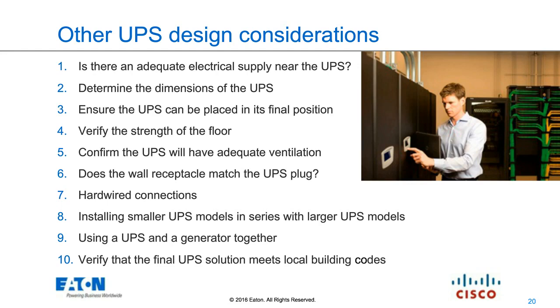And we see this a lot. This question comes up often. Putting a small UPS at the point of use with a larger UPS in the back in a utility space somewhere that's powering the whole facility. We see customers often coming in thinking that if they add a UPS at the point of use because it's closer to the equipment, that's going to increase the reliability. But the reality is that neither UPS is 100% reliable. So when you stack UPSs in series, you're actually driving your overall reliability down just a little bit. So there are some use cases for that, but it should be a one or the other situation.